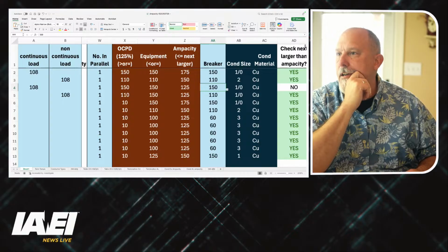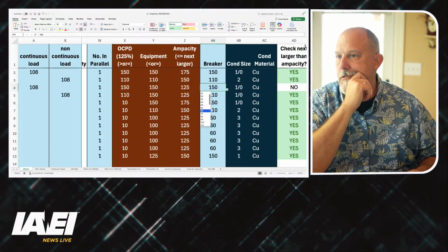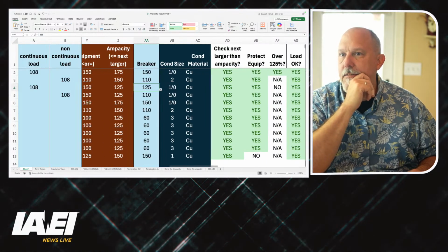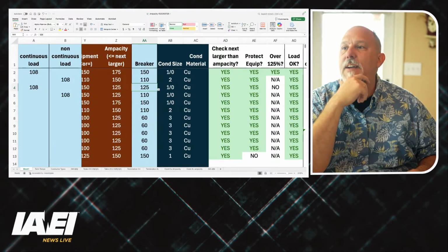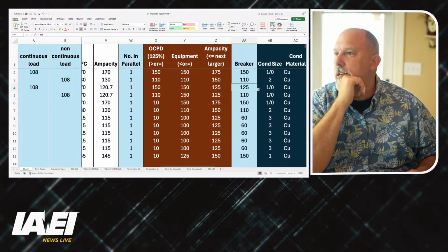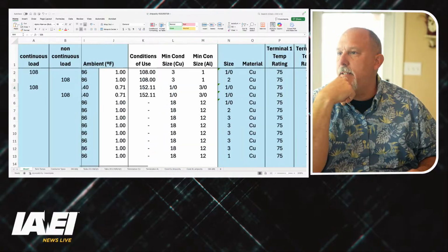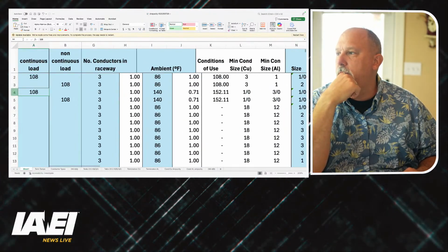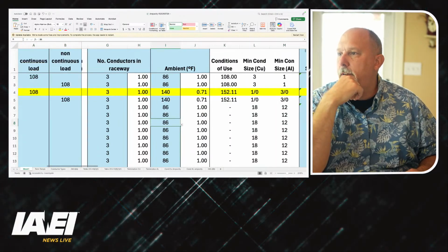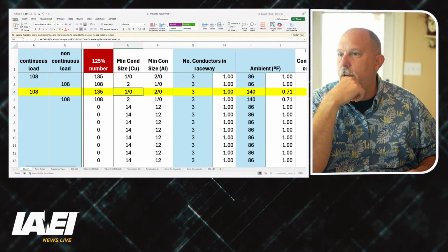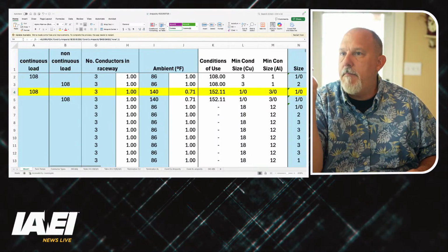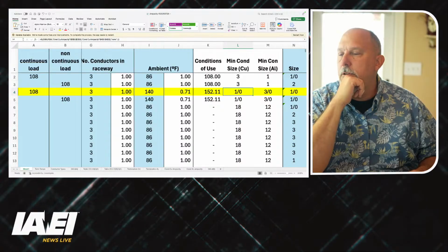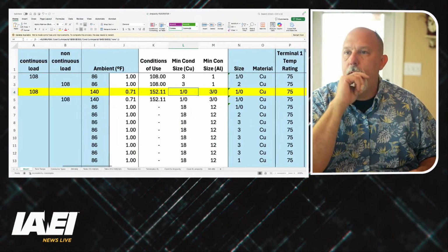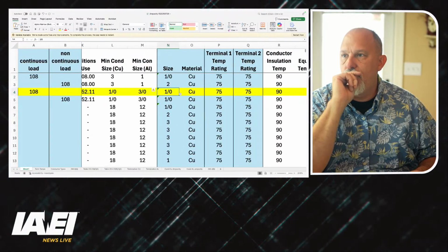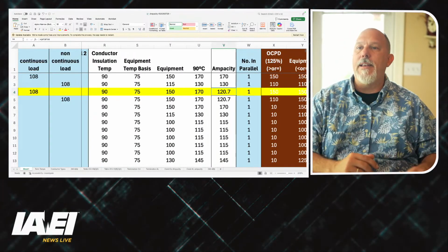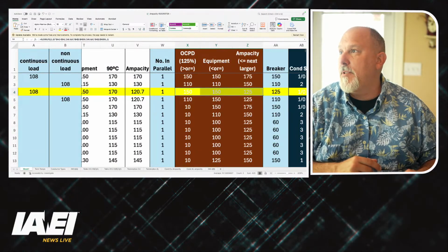150 amps for 108. I can't use 150. I've got to use 125 because of the ampacity. Boy, good thing I checked. But 125 is not over. Oh boy, wait a second. I'm going back. Let's go back. Hold on, guys and gals. I have 108 amps. I'm going to look at this one right here. Let me highlight this puppy. 108 amps worth of continuous. My minimum size is a 1/0 for the termination. My minimum size for conditions of use is a 1/0. I pick a 1/0. The ampacity is 120, so I can go to the next larger, which would be 125 amps.